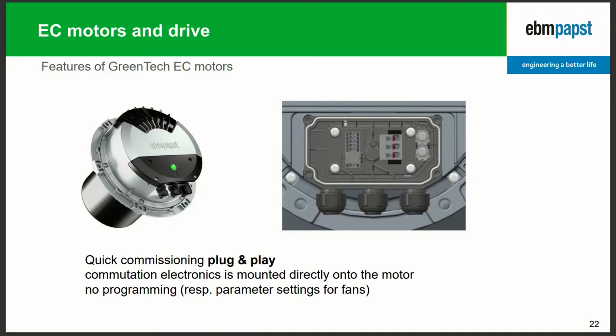And on top, every motor-fan combination is tested in our lab, every part number, and therefore it's an optimized system. You don't need to adjust ramp-up time or adjust the program, the maximum speed, etc. This is all done in the factory. So it's a real plug and play, easy-to-use product compared to an inverter where you have to go through the manual and do some settings.